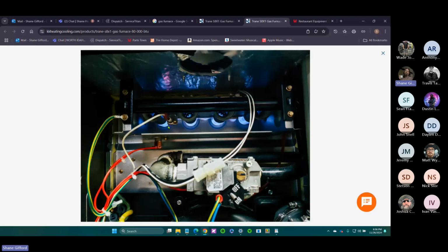Your typical gas pack, or gas furnace, or anything that's heating air, you're going to have your flame sensor, which is sitting in the burner. Most gas packs that we see won't have hot surface ignition, the glow stick, but will have an electrode pumping voltage, with a connecting rod that it arcs to. You'll see Carrier Weathermakers are the most common gas pack out there. The electrode is on one end of the burner and the flame sensor is on the other end, so as not to confuse the two. But again, flame sensor, flame rectification, the same volts DC that we were doing over here.